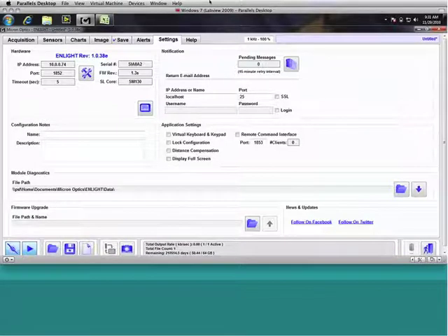One thing I'd like to point out is, in a lot of cases, as Todd pointed out, it is convenient and simpler to ignore distance compensation. However, if you are operating at some distance away from the interrogator, particularly on the SM130, you will realize a better spec, a little bit better repeatability on the measurements by putting in the accurate distance, because the instrument is now distilling the wavelength fluctuations from the correct portion of the internal reference.